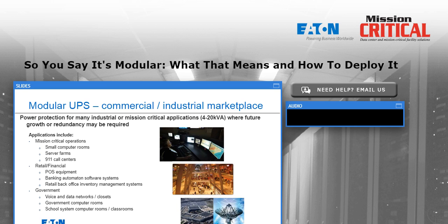Okay, so applications for this type of modular UPS might be a small computer room or a data closet like we mentioned, a server farm or a 911 call center. These, if you've ever deployed in this type of environment, sometimes they have big generators, sometimes they have no generator. Oftentimes they'll have a small generator for a 911 call center, and that generator may not have the reliability of the giant behemoths that they use in multi-megawatt data centers. So they will typically request longer battery backup time in a small UPS, and that can be easily accommodated with a modular scalable design.